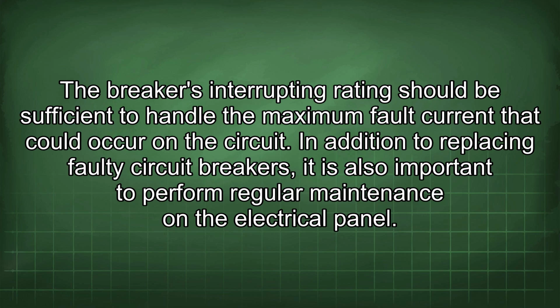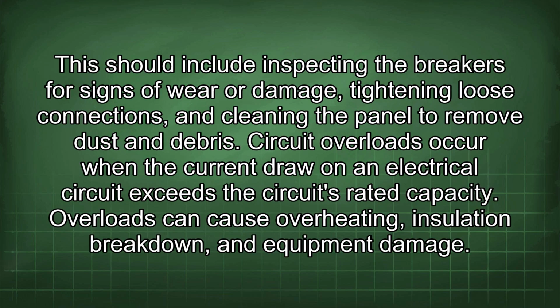In addition to replacing faulty circuit breakers, it is also important to perform regular maintenance on the electrical panel. This should include inspecting the breakers for signs of wear or damage, tightening loose connections, and cleaning the panel to remove dust and debris. Circuit overloads occur when the current draw on an electrical circuit exceeds the circuit's rated capacity.